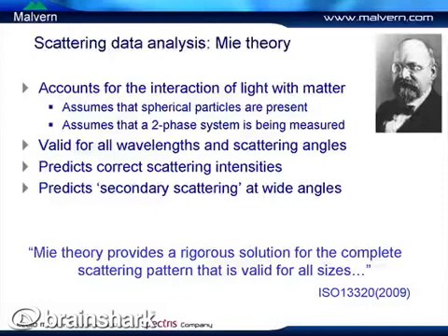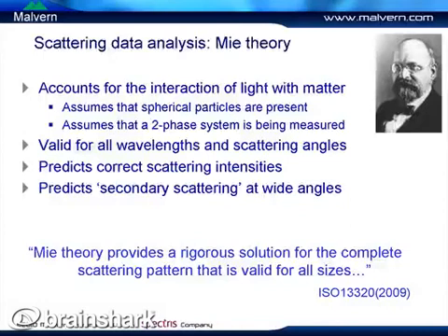Under those assumptions, MIE theory is valid for all wavelengths of light and for all scattering angles measured. With the Mastersizer series of instruments, we measure light scattering over a wide range of angles, making this model key to obtaining good results over a broad size range from 0.02 microns up to 2,000 microns. It predicts correct scattering intensities and secondary scattering at wide angles — scattering caused by the passage of light through the particle as well as diffraction from the outside surface. The new ISO 13320:2009 standard confirms that MIE theory provides a rigorous solution to the complete scattering pattern, valid for all particle sizes.